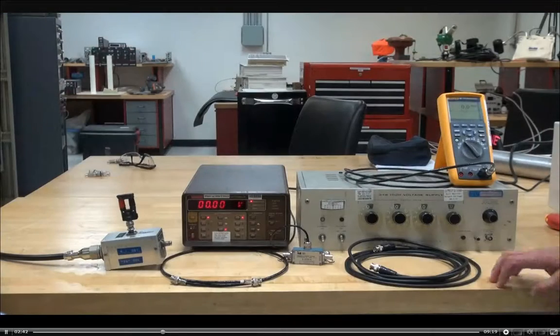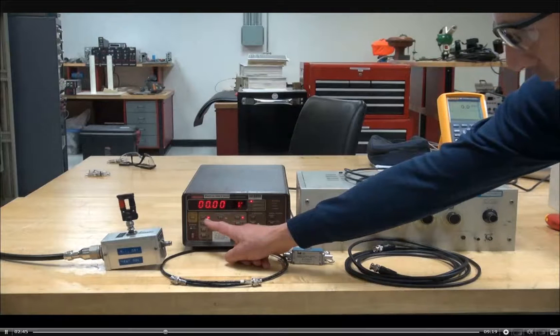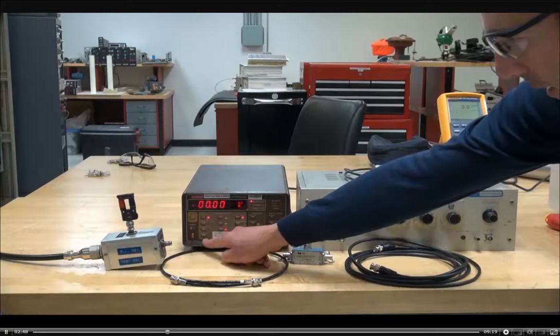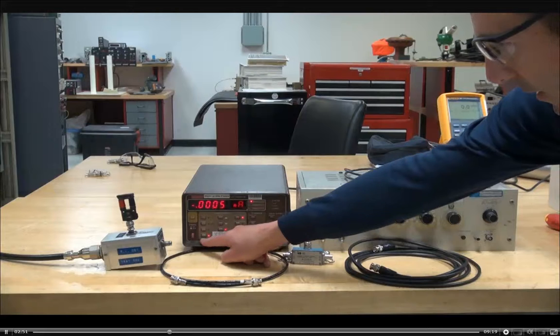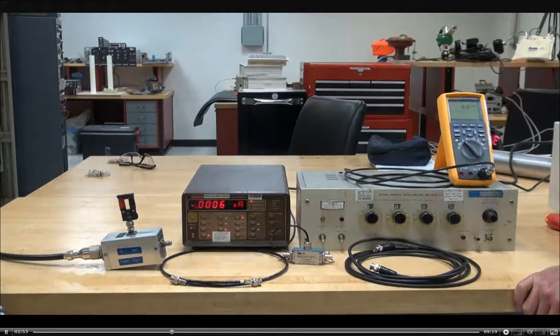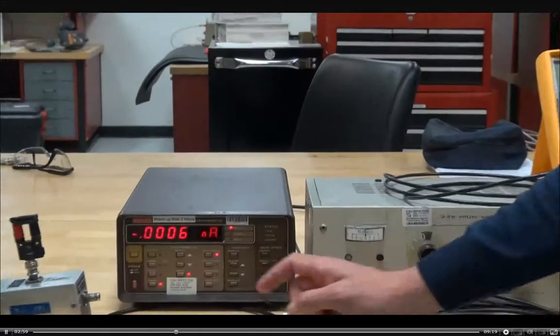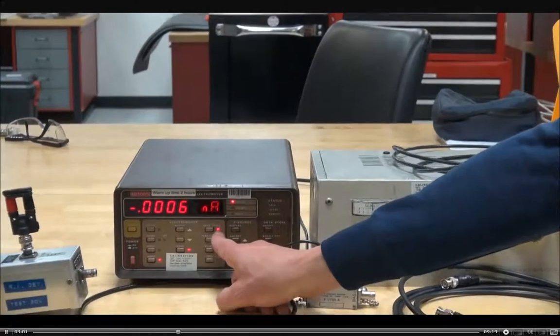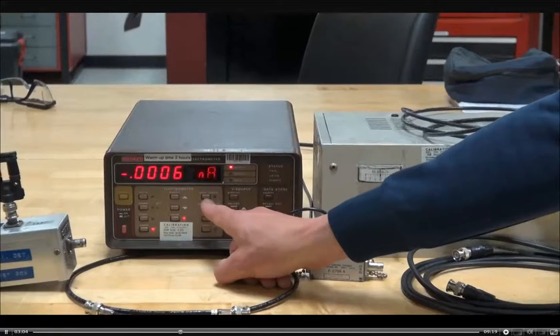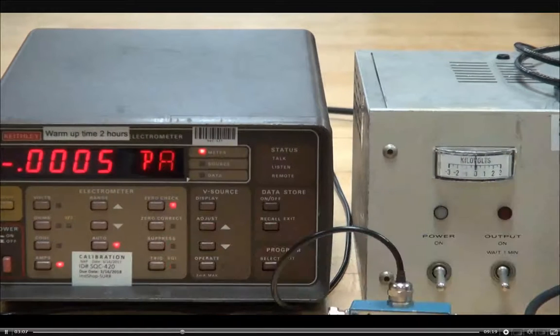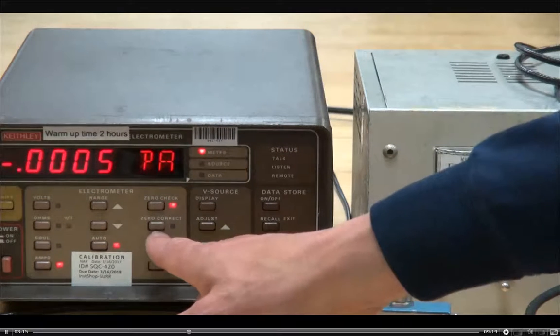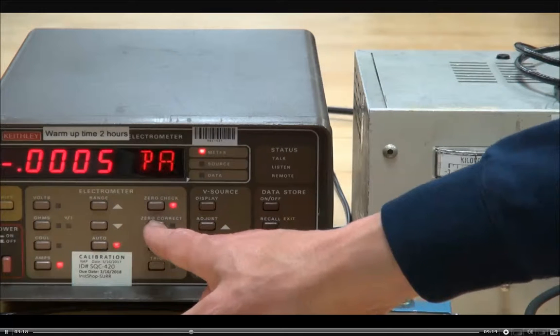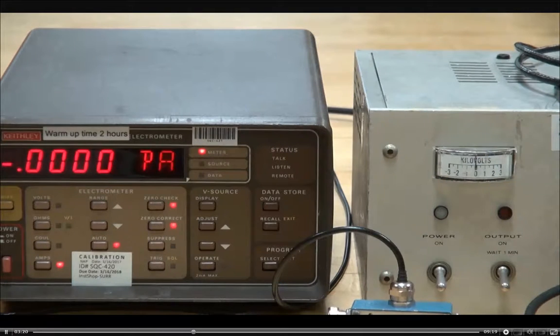Amps measurement mode is selected. When you first turn on the electrometer, it will be in the volt mode. We want to select the amps mode as the bottom button here, so we have a red light next to amps. Okay. If zero check light is not lit, then press zero check push button. Alright, usually when you turn on the electrometer, that zero check light will be lit, but if not, you can just press the zero check button and the red light turns on. Okay, press zero correct push button and check display reads 0. Alright, zero correct is right underneath the zero check, and we have a 0 indicated.